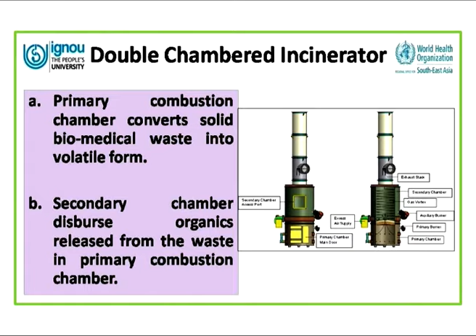The advantages of a double chambered incinerator are that it can disinfect infectious waste very effectively, reduce the volume to a large extent, more than 95%, and produce very few toxic emissions. But the disadvantage is that effective performance requires qualified operators.